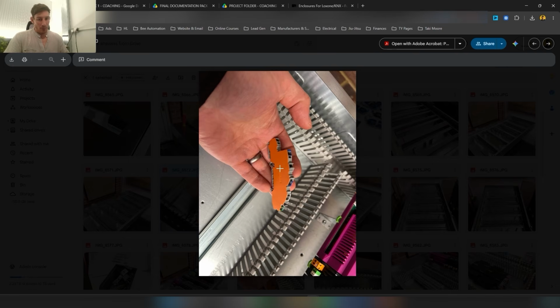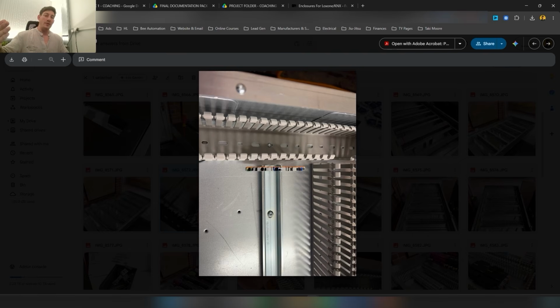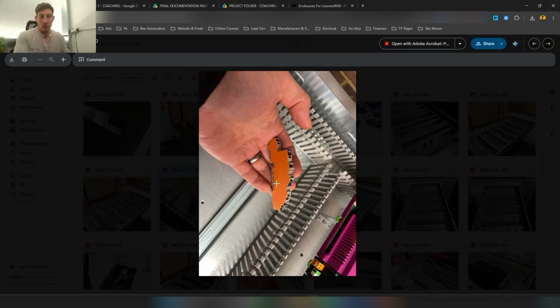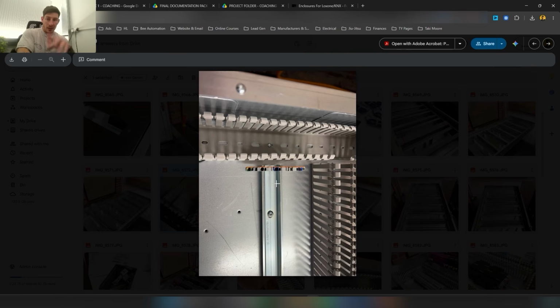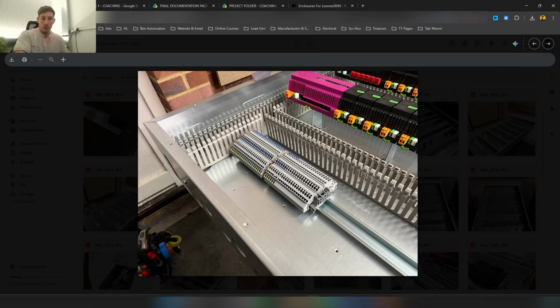This is really important to note: make sure you get some of these blanking plates, because there's always one terminal block that's going to have its internal metal contacts exposed, since there's no terminal block to the left of it. It's really important to install these, because if someone's servicing the panel, trying to get a cable, and it's live, they could easily get a shock from those exposed metal contacts and internals of the terminal block.